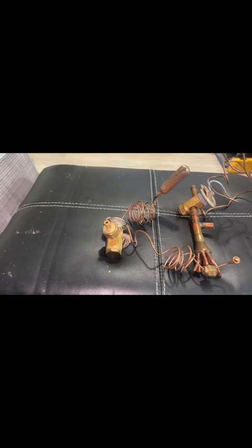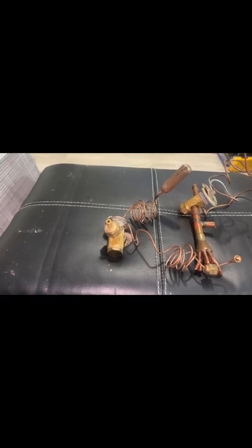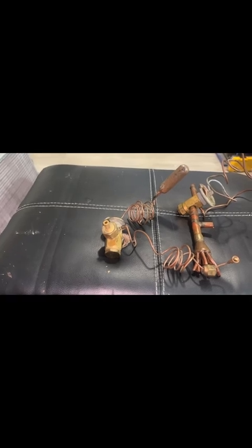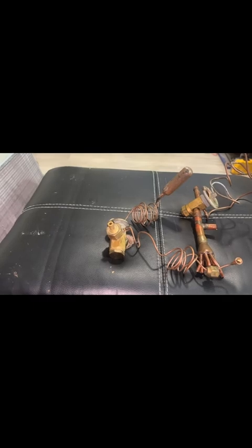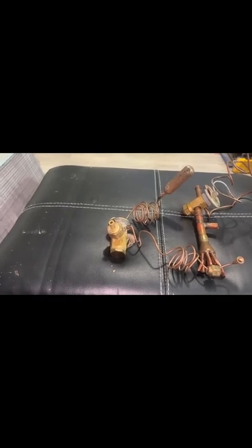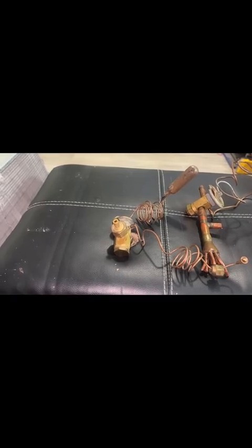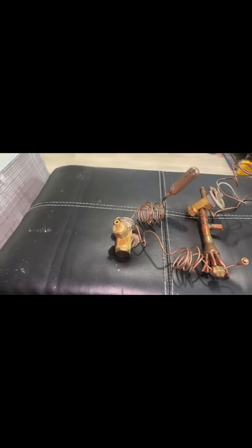Now for your heat pump systems, in a heat pump, the refrigerant flow reverses direction when switching between heating and cooling modes. Okay, so some older or basic heat pump systems use a single specialized biflow piston that can slide back and forth in its housing, seating itself to force refrigerant through the orifice in the correct direction for each mode, while allowing free flow in the opposite direction.